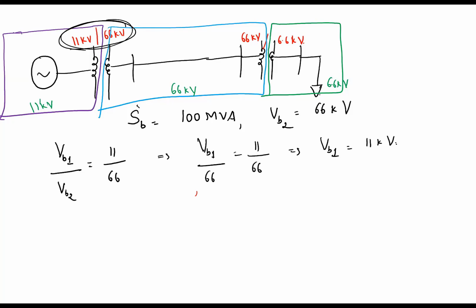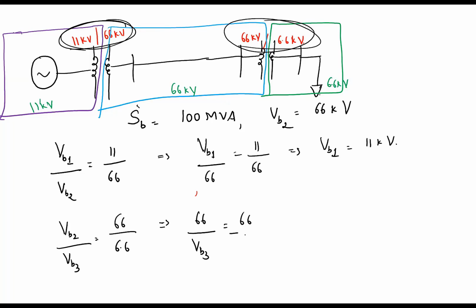So similarly, if you calculate the base voltage in section 3, VB2 by VB3 should be in the same ratio as the transformer ratio here, 66/6.6. Likewise, VB2 is 66, so 66 by VB3 equals 66 divided by 6.6, which implies your VB3 will be 6.6. Okay. So in this way, by using the voltage transformation ratio, you will calculate the base voltages. 99.99% your base voltage values will match with the transformer voltage values. 99.99%. If the examiner is a sadist, then he may give you different values.